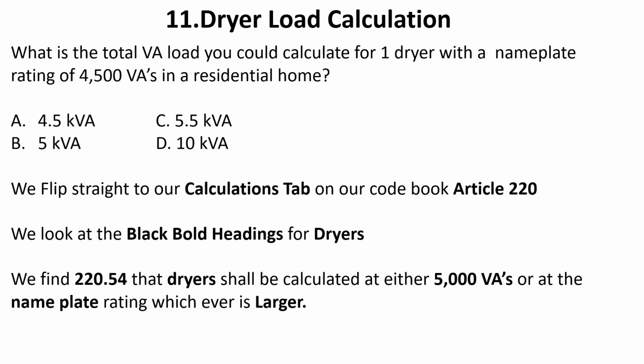Let's look at a dryer load calculation. What is the total VA load you would calculate for one dryer with a nameplate rating of 4,500 VAs in a residential home?